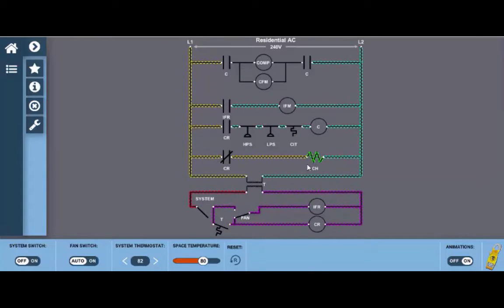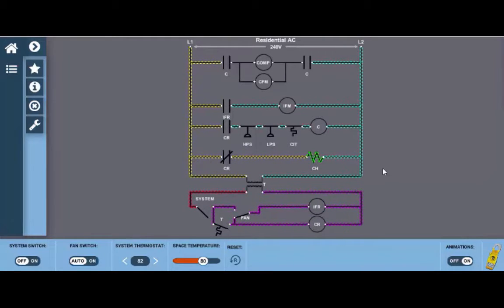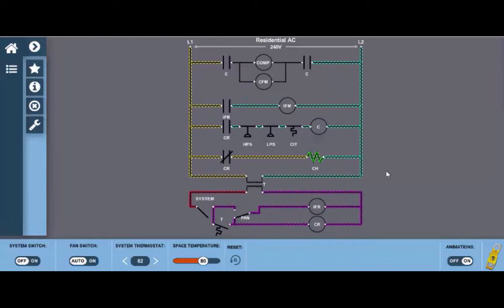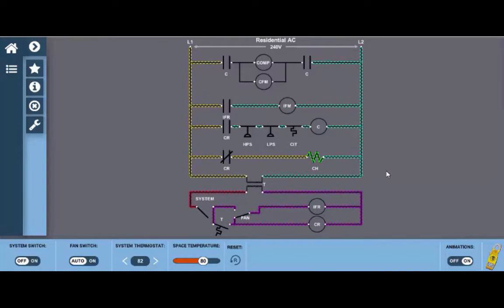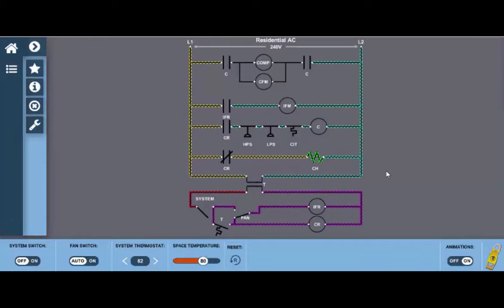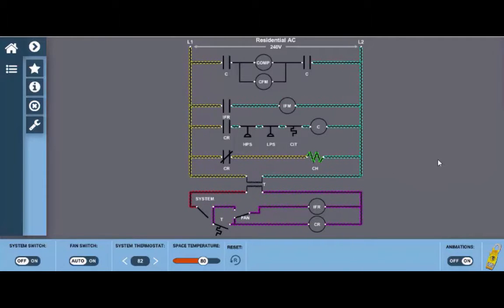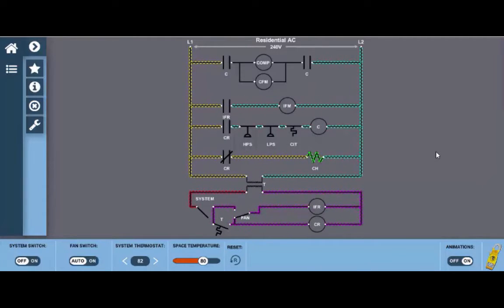What will happen typically in an off cycle is if the unit is located in a cold enough area or there's a large refrigerant charge or a really long off cycle, refrigerant will migrate as vapor to the compressor crankcase. This is where the oil is contained. This vapor will actually begin to condense in the oil and because it's heavier that liquid refrigerant will sink to the bottom of the crankcase.